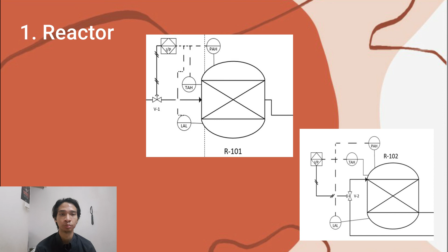For the reactor, we made some changes, such as we added a valve. We also added pressure alarm high and temperature alarm high, because we don't want the reactor to have a low liquid level, which will increase the temperature and probably will cause major injury and harm to the surroundings. So this also applies to both reactor 1 and reactor 2.